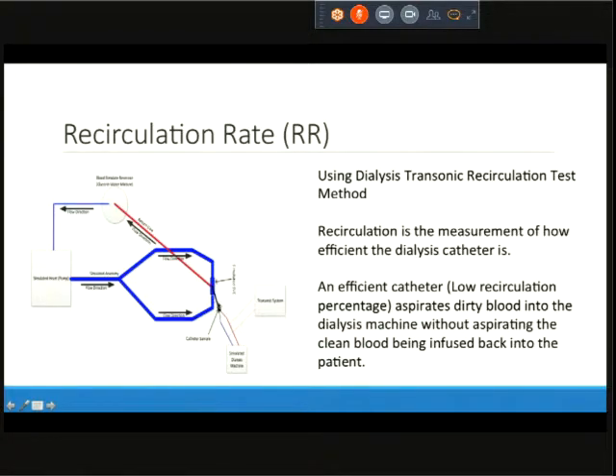And we're simulating dialysis on this end and see how much of a recirculating is occurring at the tip of the catheter, which could be the contents of the dialysis. And as you know, the recirculation is the measurement of how efficient the dialysis catheter is. And an efficient catheter with a low recirculation percentage basically means it aspirates the dirty blood into the dialysis catheter without aspirating the clean blood being back into the patient.